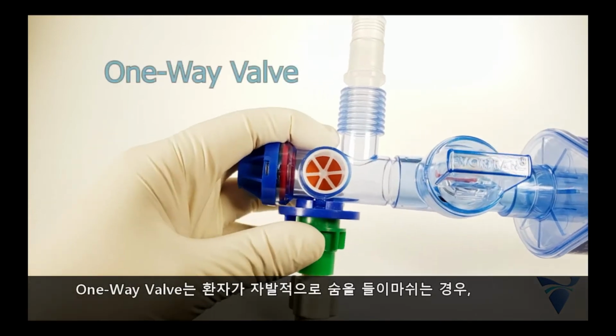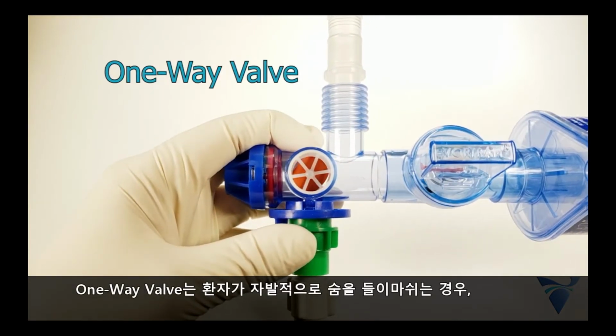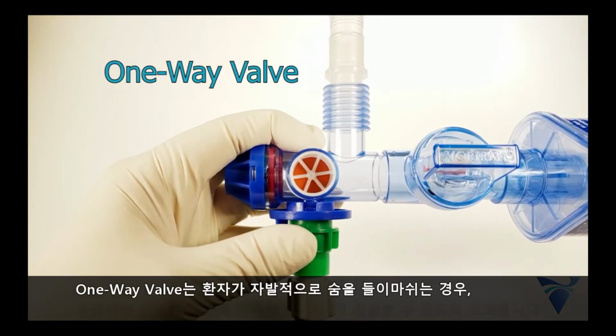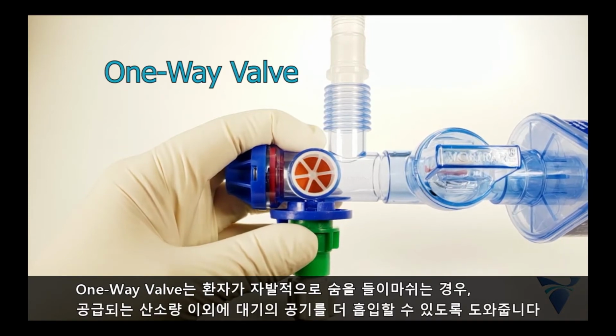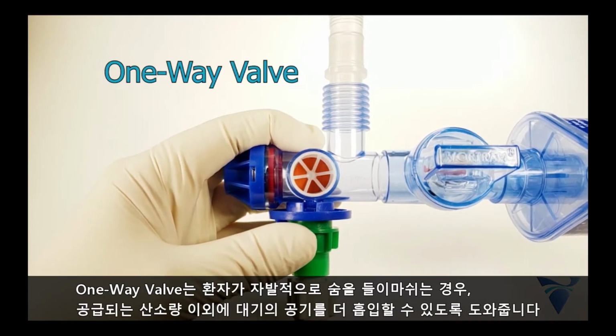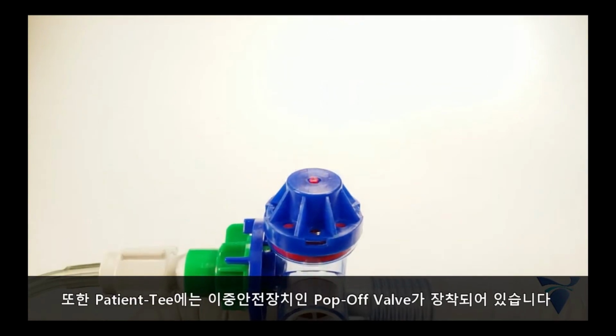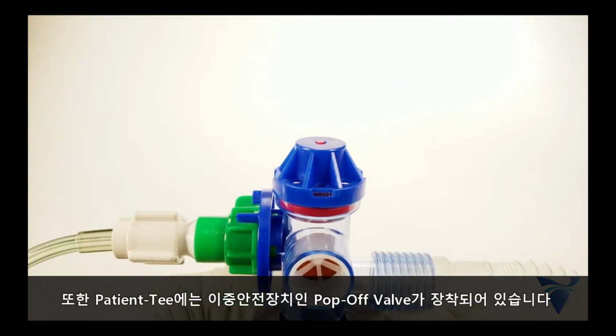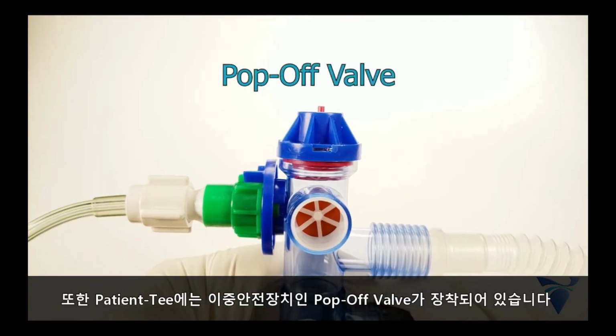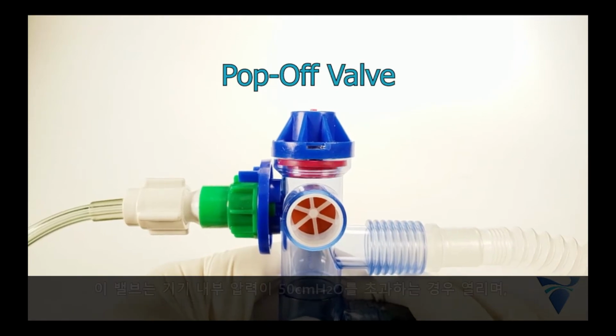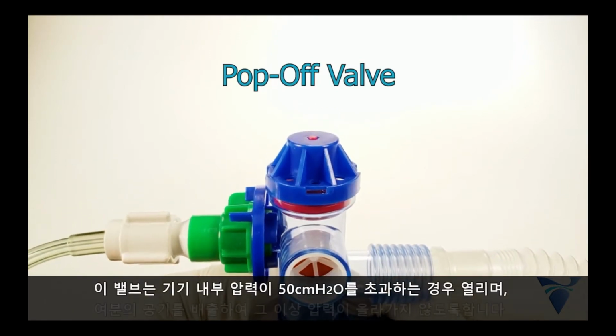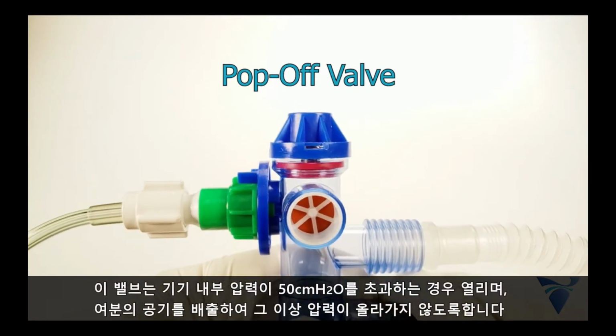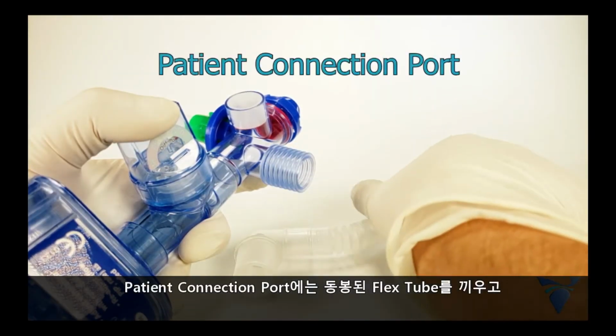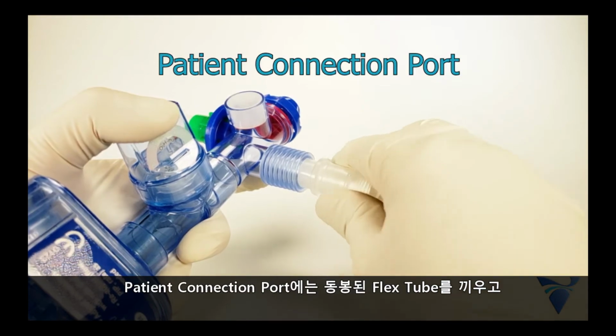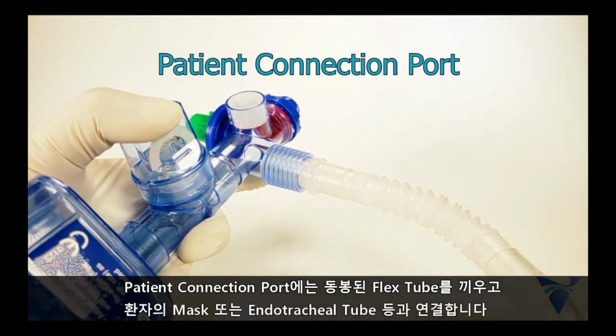A one-way valve allows the patient to entrain additional ambient air if a patient's spontaneous inhalation demands more flow than is being provided from the oxygen source. Also contained on the patient T is a redundant safety valve, referred to as the pop-off valve. This valve will open and relieve pressures that reach above 50 centimeters of H2O.